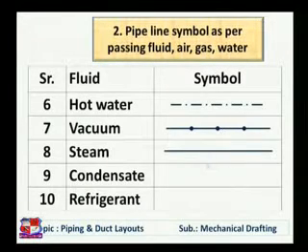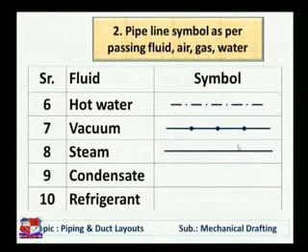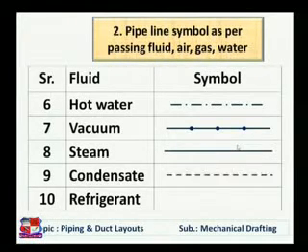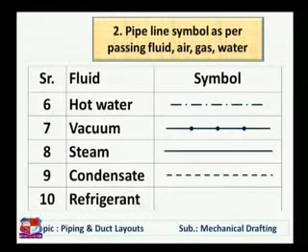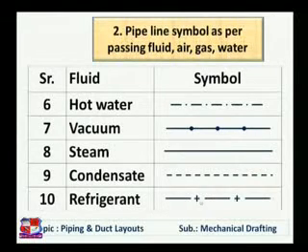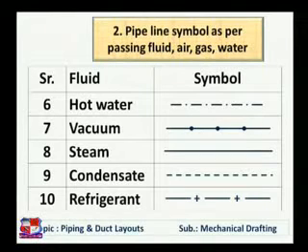Steam passing through the pipeline is shown by a thin line. In the previous case, cold water used a thick line; in steam, a thin line is used. Sometimes steam properties are mentioned, such as pressure, dryness fraction, or temperature. To show condensate passing inside the pipeline, a dotted or dashed line is drawn. To represent that some refrigerant is passing through the pipeline, a plus-plus symbol is drawn, which happens in refrigeration and air conditioning circuits such as VCR or VAR circuits.